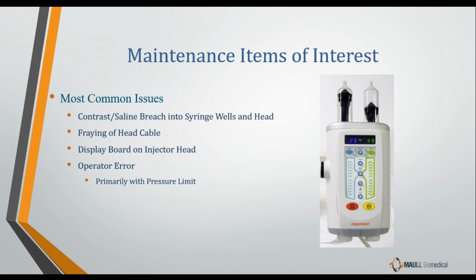They're not quite using it right. The biggest one, primarily, as I mentioned earlier, is they're not programming the pressure limit properly. So they'll call you up saying the injector's shooting too slow, or the injector has shut down, or it didn't shoot the amount of fluid that they thought. Typically, those things are not legitimate issues. It's just the operators not using the machine quite the way it was designed to be used.